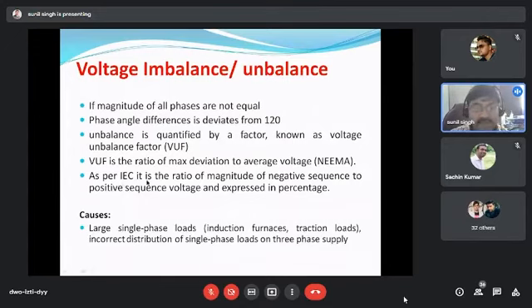As per the IEC definition, it is the ratio of the magnitude of negative sequence to the positive sequence voltage, expressed in percent. It is nearly similar to that definition. What is the negative sequence voltage? You know that whenever the three-phase supply becomes unbalanced, then as per the theorem, we can decompose this unbalanced supply into three balanced supplies known as the negative sequence, positive sequence and zero sequence. The negative sequence arises because of the unbalance. So the numerator, the maximum deviation, we can equate to the negative sequence voltage. It is the magnitude of the negative sequence voltage, not the angle.